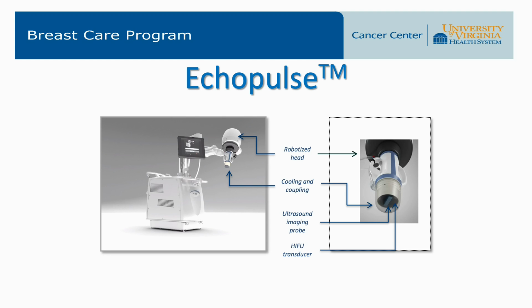We've used the EchoPulse device for all of our breast cancer studies, and it consists of a computer-driven system comprised of an electronics cabinet, an extracorporeal probe mounted on an arm and moved by motors, a cooling unit, and an ultrasound imaging probe that is mounted within the HIFU transducer. Here is the business end of the device. This is the roboticized head. This is a cooling jacket through which cool liquid circulates to keep the skin cold during the treatment. This is the ultrasound probe that is embedded within the HIFU transducer.